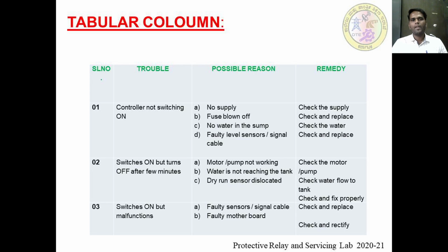Next is the controller switches on but turns off after a few minutes. This is mainly because the motor or pump is not working properly. There might be water not reaching the tank because of foreign bodies obstructing the pipeline, or there might be a dry run sensor dislocated.